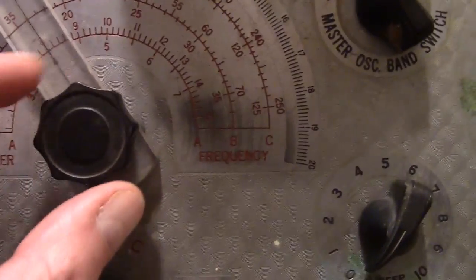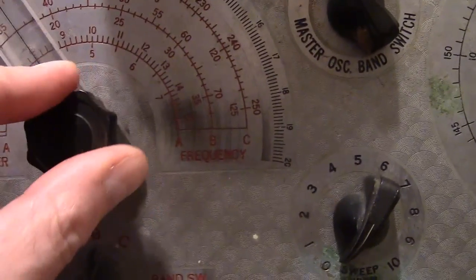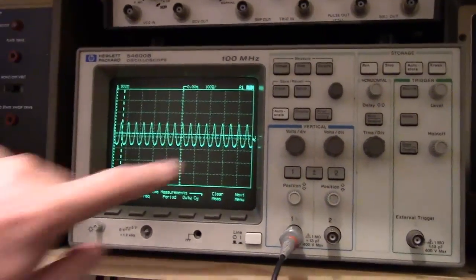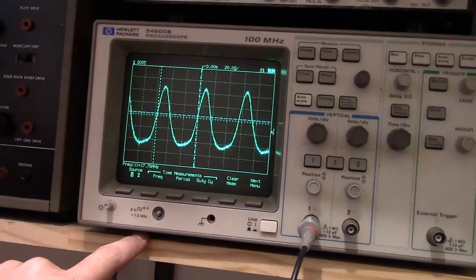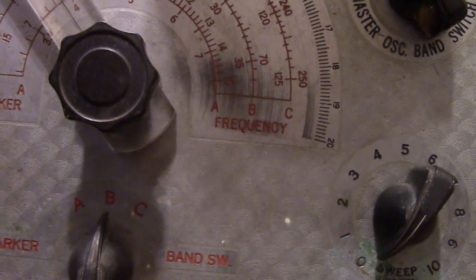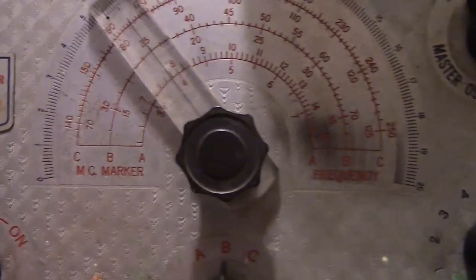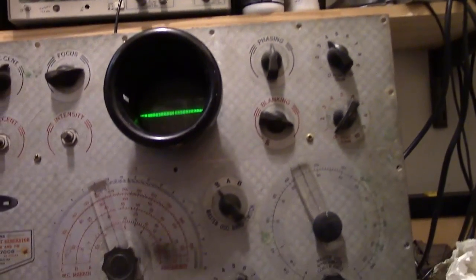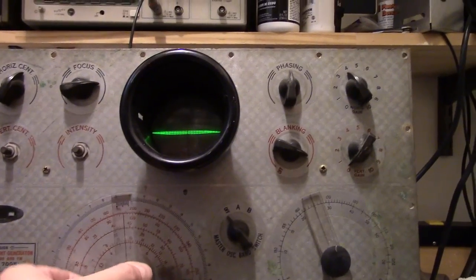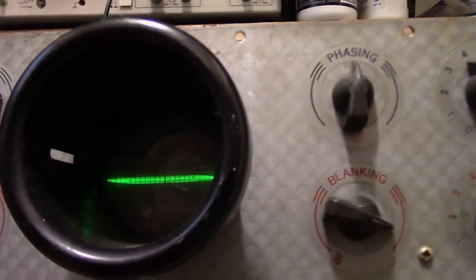Jeez. That's pretty impressive. But the B band, let's see, this should be 35. And it's measuring about half of that, actually. 17 instead of 35. Oh, I see that there are marks on both sides of that. Might have something to do with harmonics. So let's go up to here where it shows 20. And now we're at about 20 megahertz. Well, this thing might actually be fairly well within calibration. Speaking of which, if you do cal, you're supposed to see something on this, but I gotta read through the manual a bit more. Certain frequencies, yeah, we kind of get something like right there. Try increasing the vertical gain.